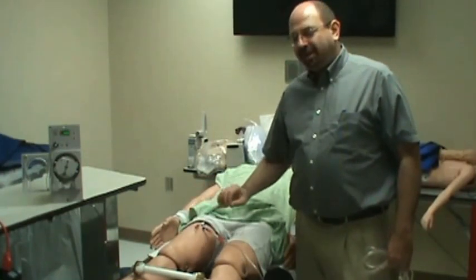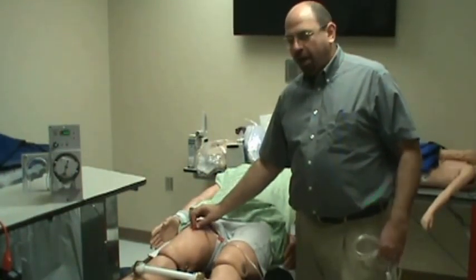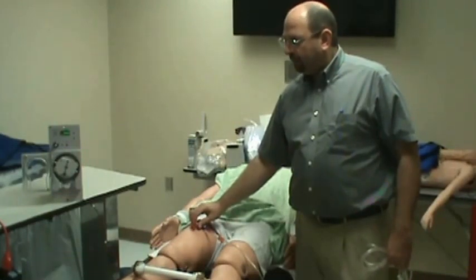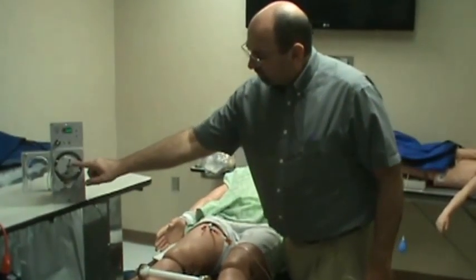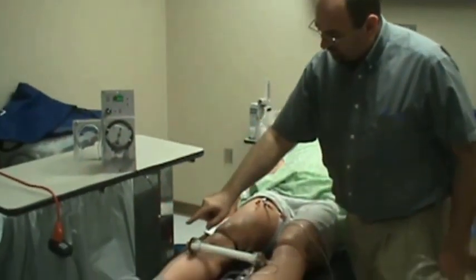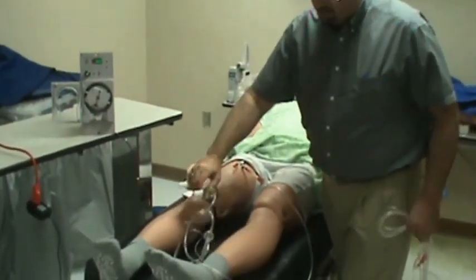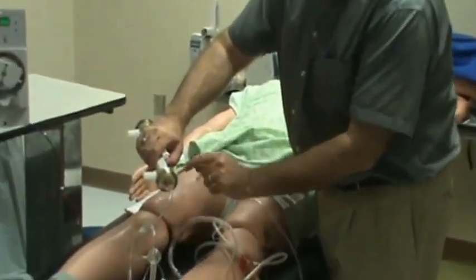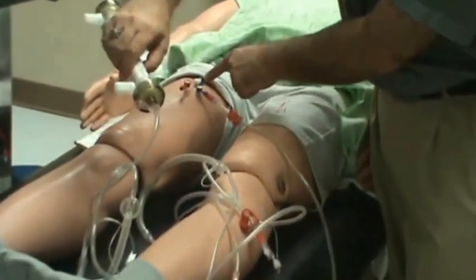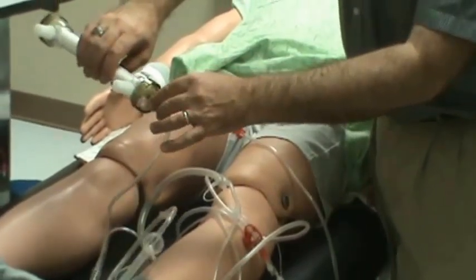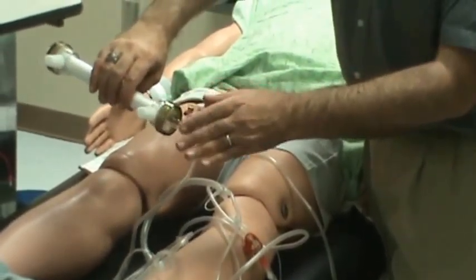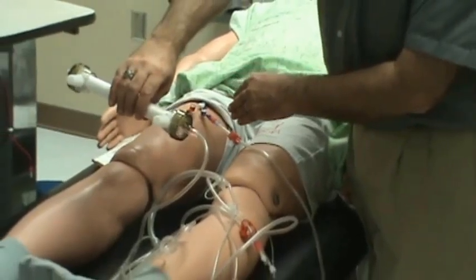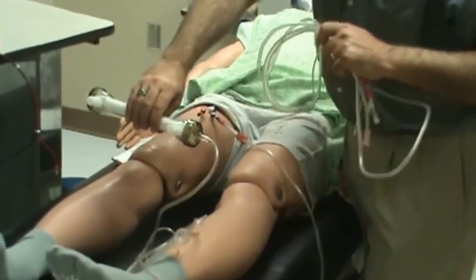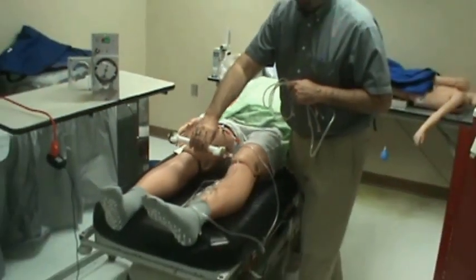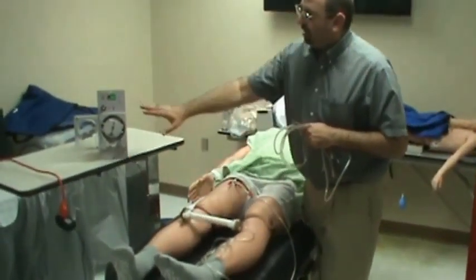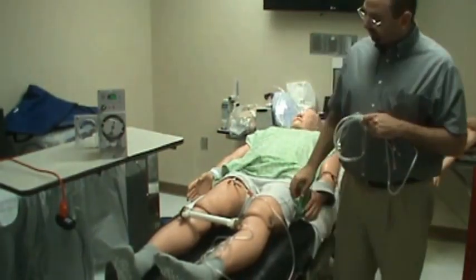So, when we talk about the connection, we're going to connect our tubing from the arterial limb to the pump, and then to the filter, and then back from the filter to the venous system, back to the patient. So, this has already been connected and primed in order to show you that now the venous return is very easy. What I'm going to do is demonstrate how to connect the arterial side and how to connect into the pump. Mind you, this is a pump.